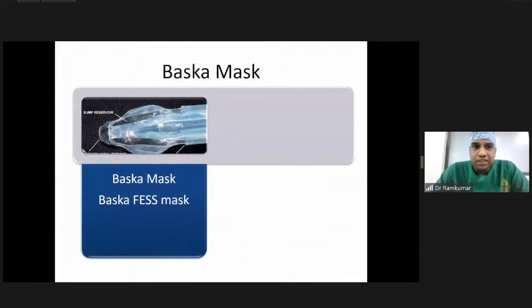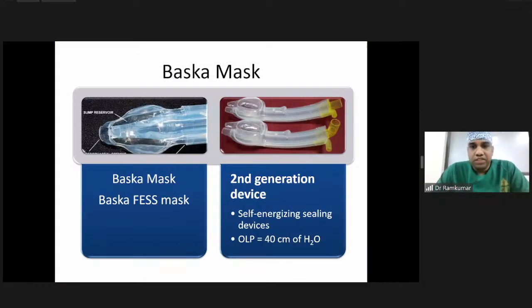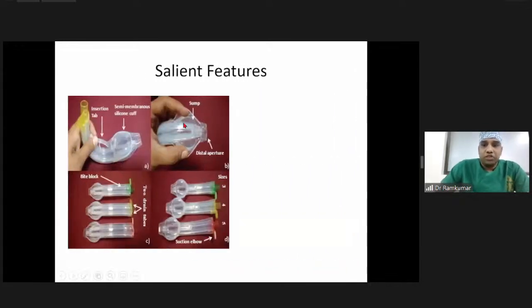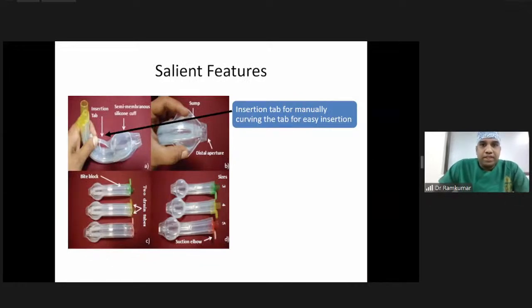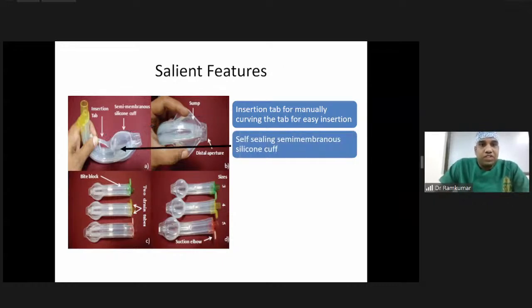Baska mask. The Baska mask is a silicone device. It's a disposable silicone device, still considered a second generation device. The important aspect is the self-energizing sealing mechanism, and the posterior aspect is the sump. It is connected to the tip, so all the gastric contents can be collected and aspirated through the drain tubes on either side. The oropharyngeal leak pressure, as studied and as the manufacturer claims, is around 40 centimeters of water. The feature here is a tab which, when pulled, makes it a preformed anatomical curvature like an ILMA, so it can be inserted without a sniffing position. If a patient has a C-spine fracture or difficult neck extension, this can be used to insert it. That's the advantage of the Baska mask.